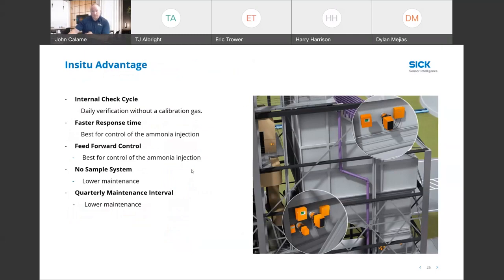So one of the huge advantages for the in situ device is we have the capability to mechanically do our daily validations with zero reflectors and span filters to do your daily checks and verifications without calibration gas. And we all know that calibration gas, cylinder gas, is expensive to procure and to maintain. So you can think of how much it costs you for a cylinder of gas. And if you had to do that 365 days a year, maybe you're going through a cylinder per quarter, so that's 4 cylinders, or maybe you're going through one a month.